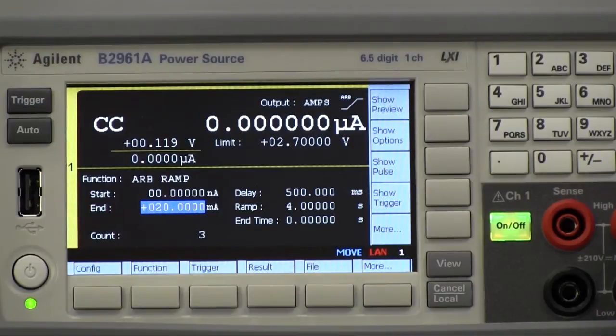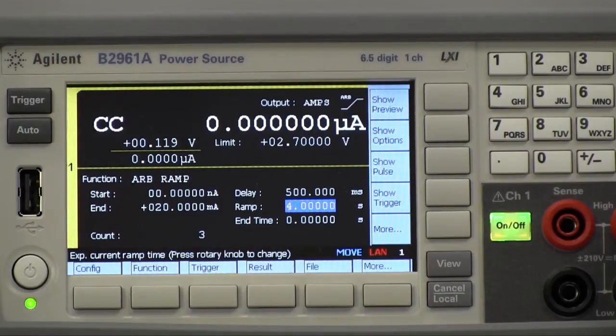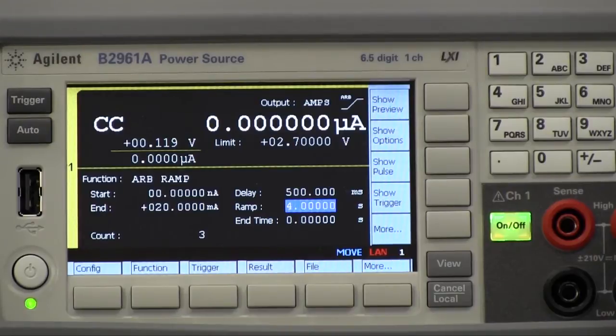And I want to make sure that I have the proper ramp time and number of steps. So I've got three set here and also we've got a four second ramp. So this basically completes the setup.